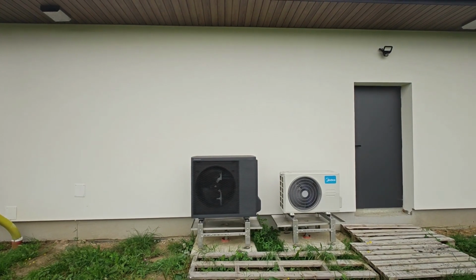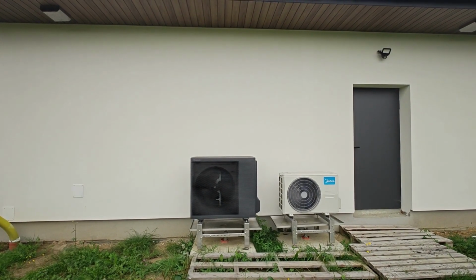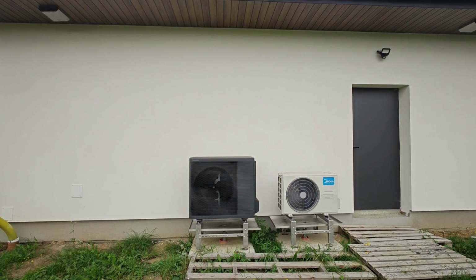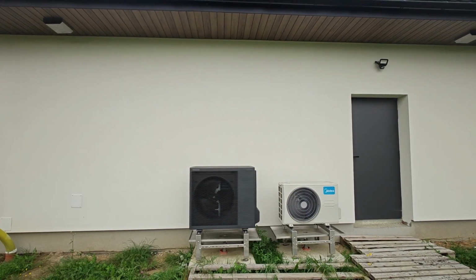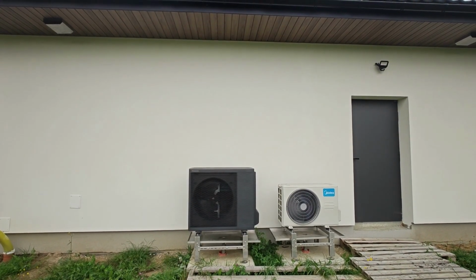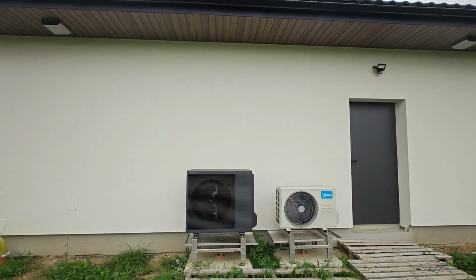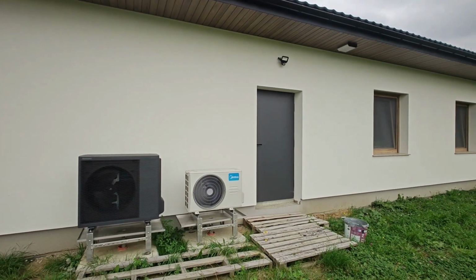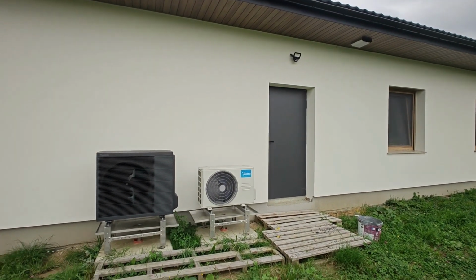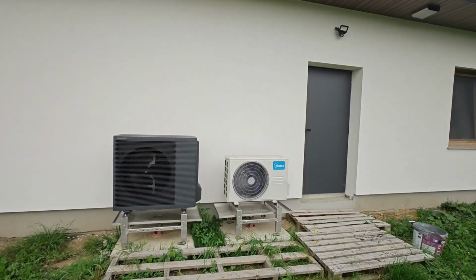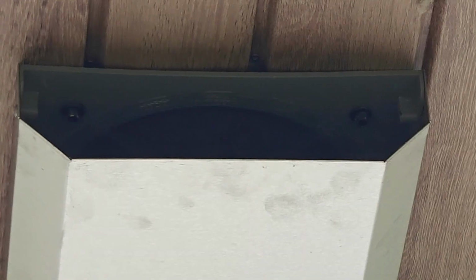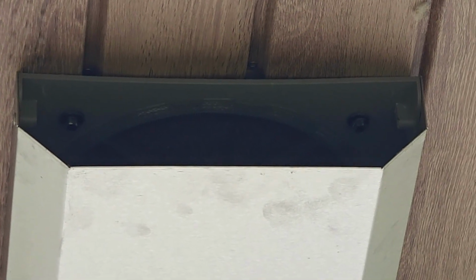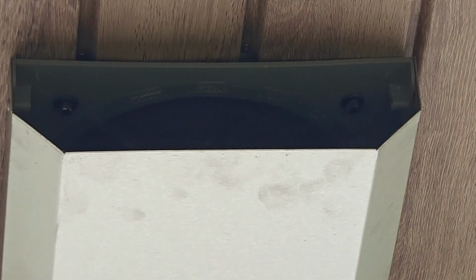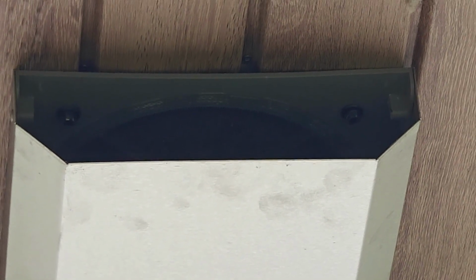Starting from the beginning, and outside the building, on the northwest side of the building, there's an air intake. Here in the video, it's on the left side, and the exhaust is on the right side. On the underside, to be exact. The white unit you see down below is the air conditioning unit. Both the intake and exhaust units have an integrated stainless steel mesh to prevent impurities from entering the system.